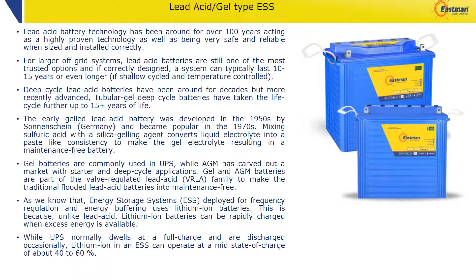In continuation, unlike lithium batteries, lead acid battery banks do not have a specific cutoff point at a certain depth of discharge. So in an emergency situation where you need to draw excess energy, they can continue to provide power backup until the voltage reaches the inverter cutoff, although this does affect battery life. But unlike a lithium ion battery, they're not controlled by a BMS — they can be used as much as needed in times of emergency. This is one of the most important standout points of the lead acid battery.